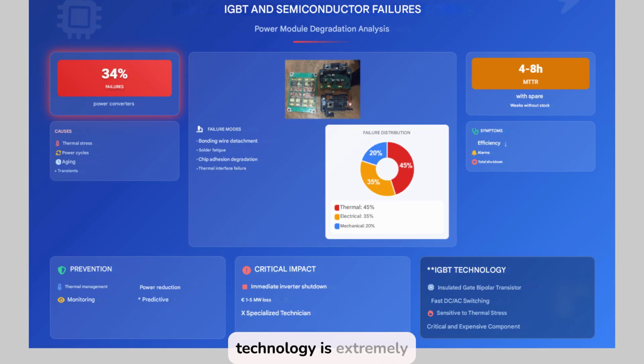IGBT technology is extremely critical in inverters. It allows rapid switching between direct and alternating current and operates under highly demanding thermal and electrical conditions. Due to its complexity and sensitivity, this type of component cannot be replaced by non-specialized technical personnel. Specific training in power electronics is required. Some maintenance strategies should include availability of critical spare parts in key locations, strategic stock, continuous thermal monitoring using embedded sensors or advanced SCADA systems, scheduled inspections to check the integrity of welds, interfaces, and heat sinks.